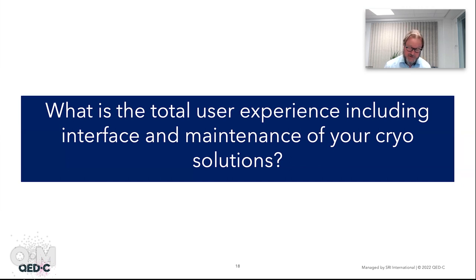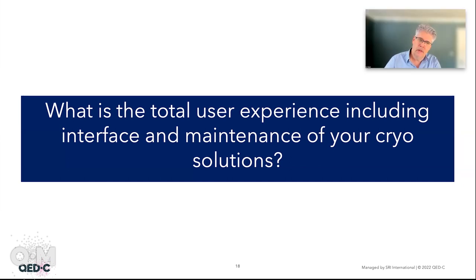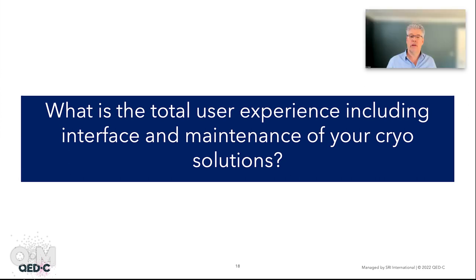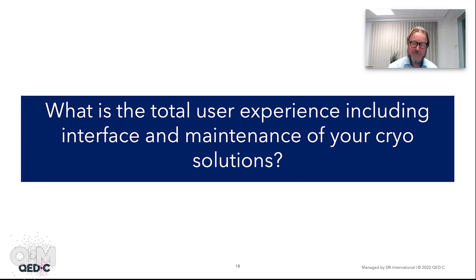So it's self-running. And how about the maintenance? So the systems were made to be maintenance-free for 3 years from the start. But of course, the more critical your operation is, the more you need predictable operation, and you need to have preventive maintenance, etc. There are components from the best manufacturers that are used. But as someone mentioned earlier, they are mechanical devices, and they need to have attention. And in our new software developments, we are looking more and more into how you can have a more predictive model for these mechanics that are in these systems.